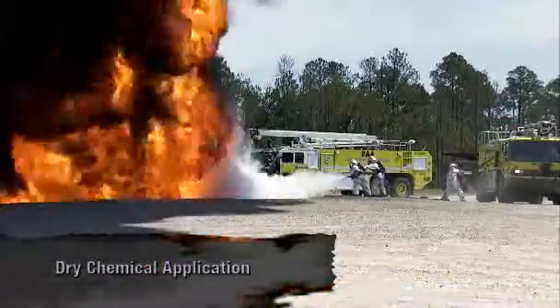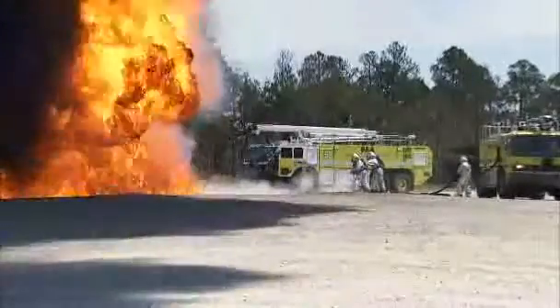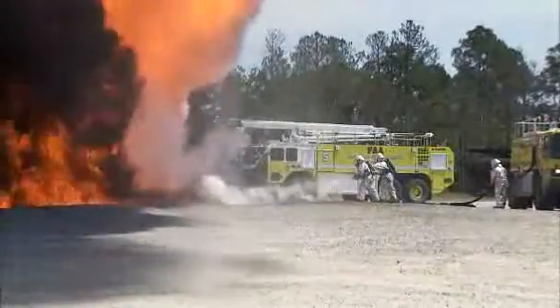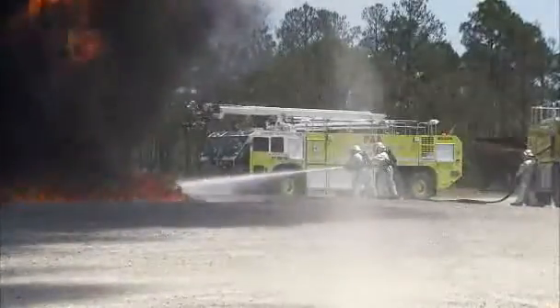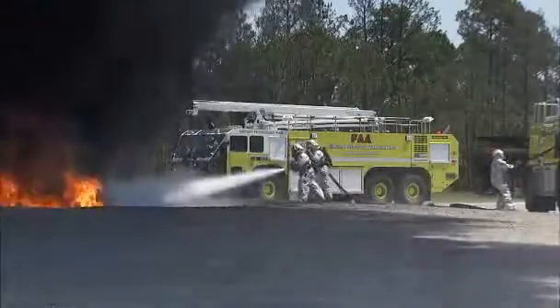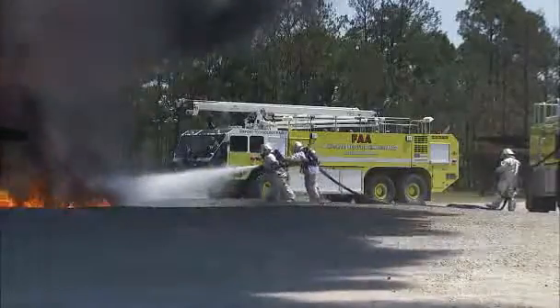Apply dry chemicals by directing agent at the base of the fire and sweeping the nozzle back and forth. Charge and test the system by discharging the agent before approaching the fire from upwind. Check range by discharging small bursts at the fire. Start the initial application from as far away as possible. Handlines from large wheeled extinguishers and truck-mounted systems have significant nozzle pressure. Brace yourself and have someone back you up.